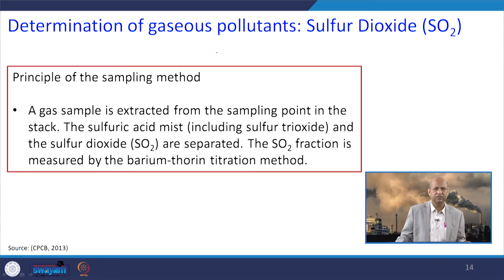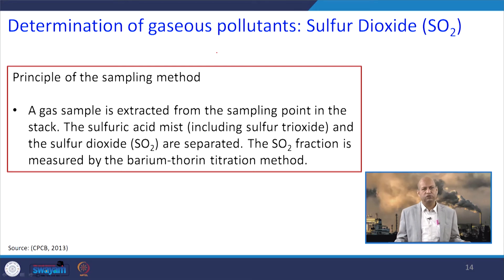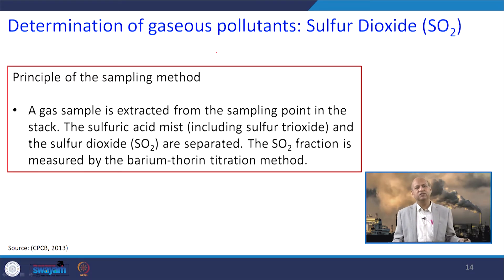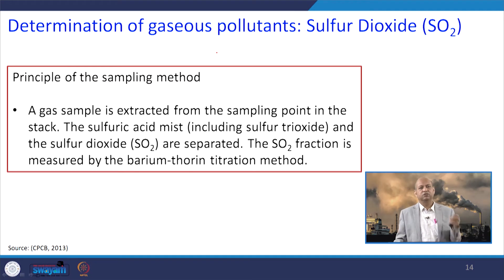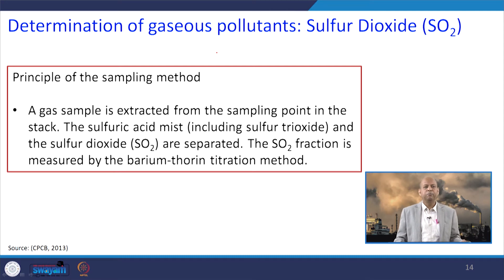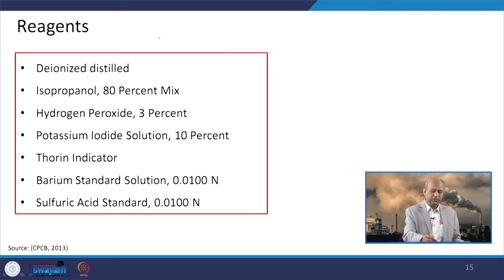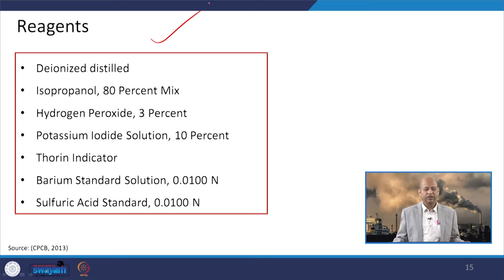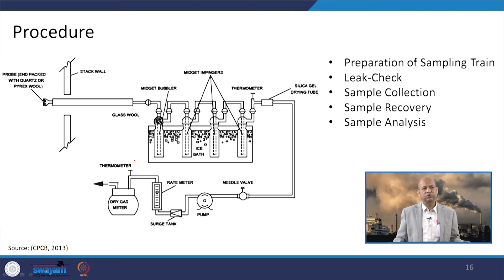This device can also be used for monitoring gaseous pollutants by using impingers. For SO2, gas sampling is done through extraction from the sampling point using the probe in the stack. In this case, sulfuric acid mist including sulfur trioxide and sulfur dioxide are separated to avoid error. The SO2 fraction is measured by the barium thorin titration method. Reagents used include deionized distilled water, isopropanol, and 3% hydrogen peroxide.